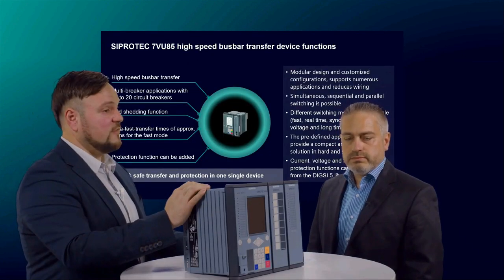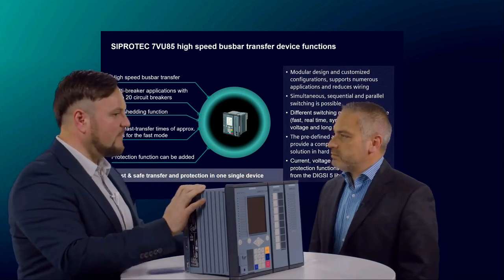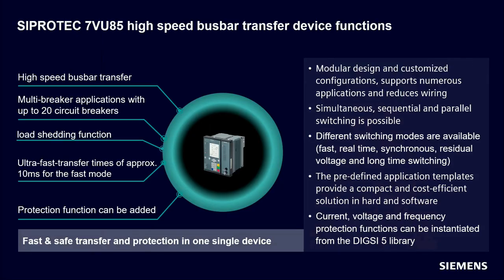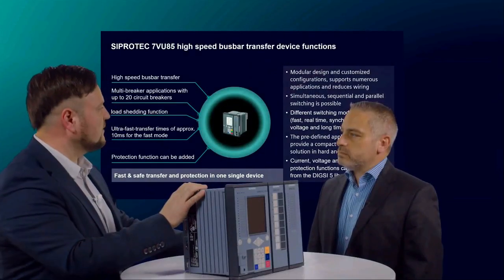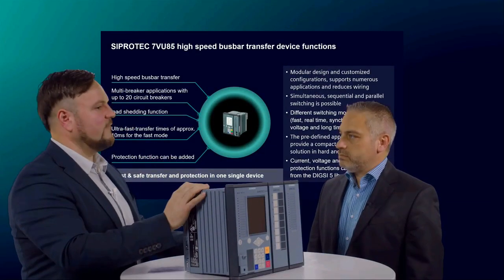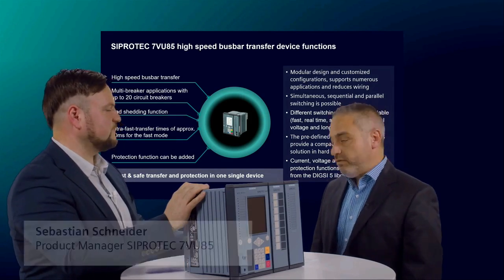And what are the main tasks of the HSBT function? Yeah, the main task of the HSBT is that the 7VU high-speed busbar transfer device continuously monitors the voltage on the main incomer, the motor bus, and the alternative incoming feeder. The functionality automatically disconnects a faulty incomer and transfers bus load to an alternative power source. This ensures an optimum transfer with minimal impact on the production processes and no risk of damaging electrical equipment. This feature avoids expensive and unplanned shutdowns.